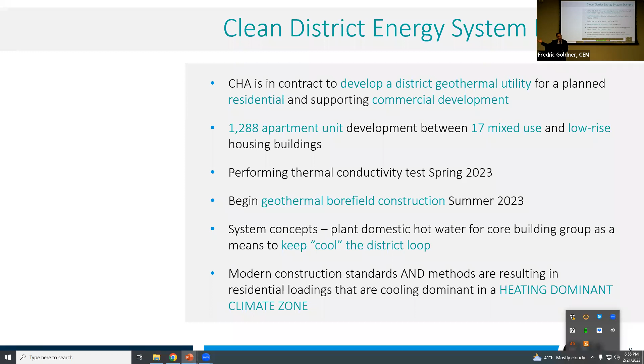Doing some math, I determined this is a good, feasible solution to my warming loop. The penalty is that the domestic water plant is estimated to cost $1.5 million, or basically 5,000 MMBtus of energy needed to handle the daily water load of those core buildings. But it sure beats a cooling tower, it beats the pumps sending fluid to a remote cooling tower behind the shack, and the maintenance man who has to know how to take care of that cooling tower.